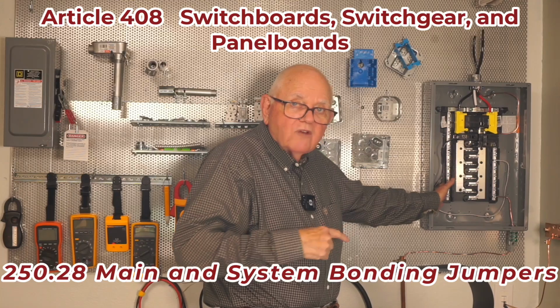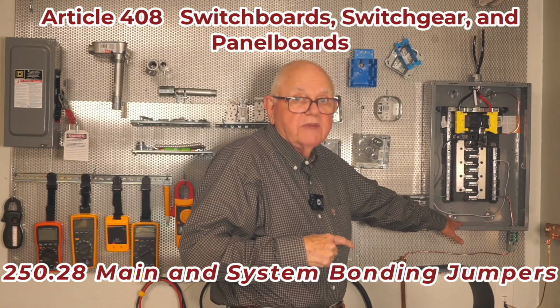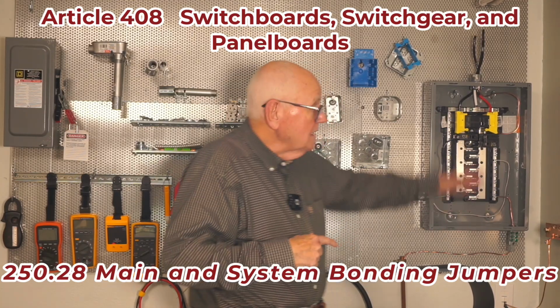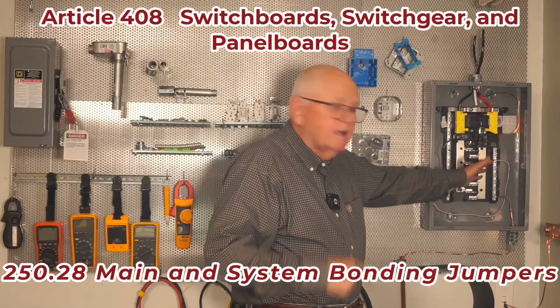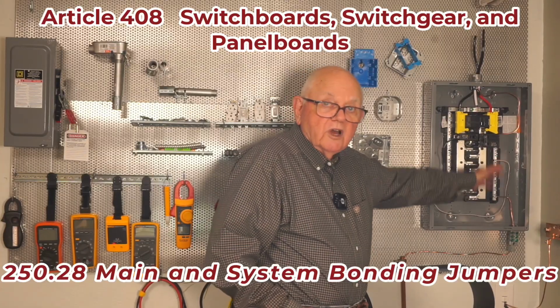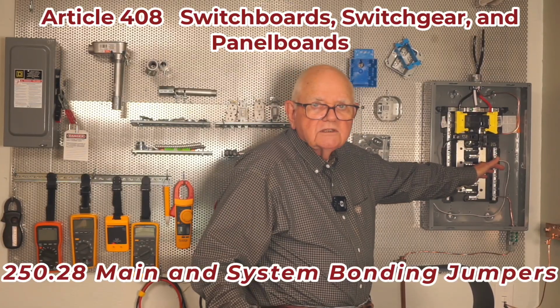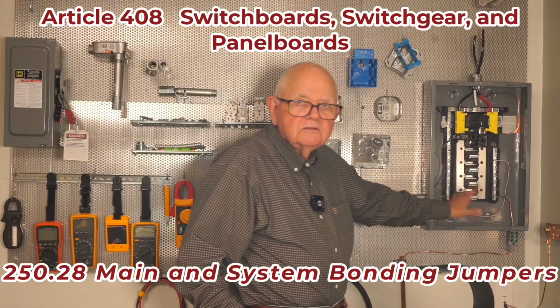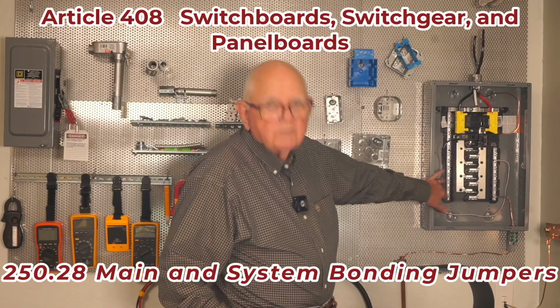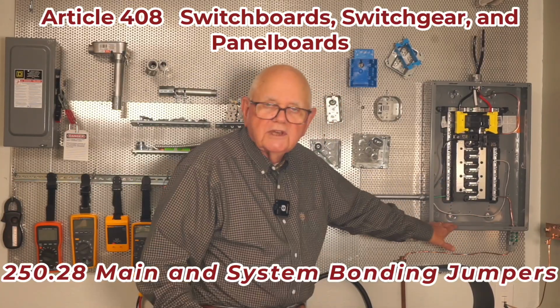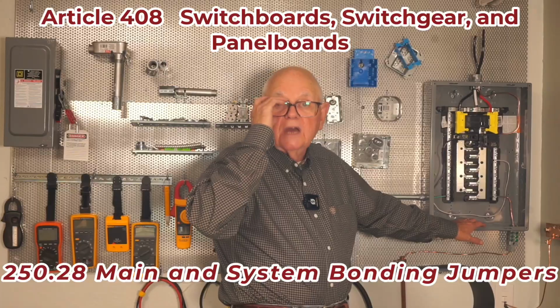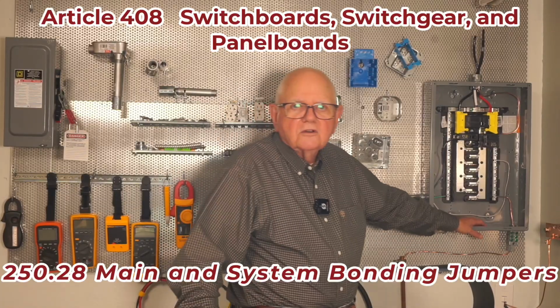The equipment grounding bus bar is already bonded to the metal enclosure. So what have I done? I've taken my incoming neutral that goes to my neutral bus bar, all my neutrals as well, and I have connected them to the metal frame and the equipment grounding conductor. I bonded those three things together. We call that the main bonding jumper, and it's all covered in Article 250.